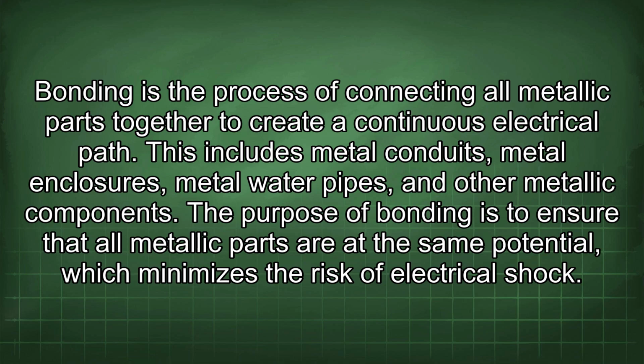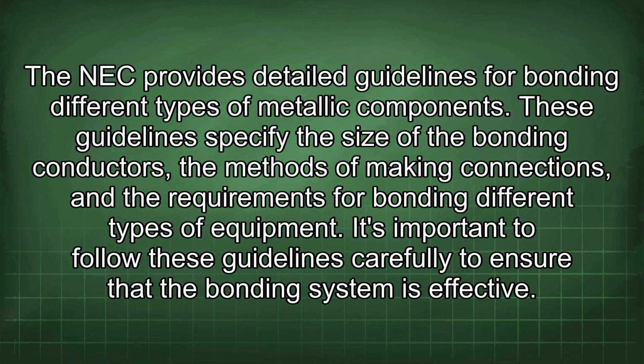This includes metal conduits, metal enclosures, metal water pipes, and other metallic components. The purpose of bonding is to ensure that all metallic parts are at the same potential, which minimizes the risk of electrical shock. The NEC provides detailed guidelines for bonding different types of metallic components. These guidelines specify the size of the bonding conductors, the methods of making connections, and the requirements for bonding different types of equipment. It's important to follow these guidelines carefully to ensure that the bonding system is effective.